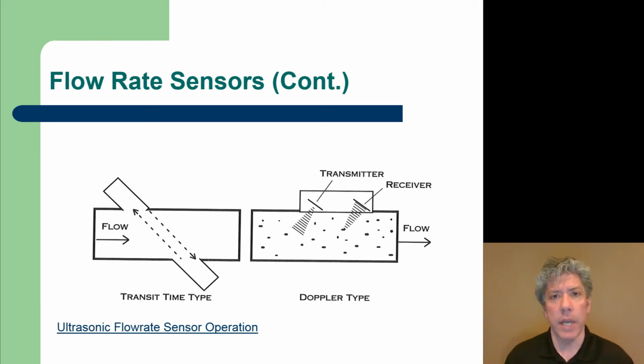And the reason for that is because of the motion of the train itself. Well, that idea is being used in the Doppler type flow rate sensor, where a transmitted pulse is sent out, reflected off of particles in the flow, and received by a receiver. Now, because the particles are moving, they will change the frequency of the sound, and that shift in frequency can be detected so that the particle speed can be inferred, and therefore the flow rate inferred.